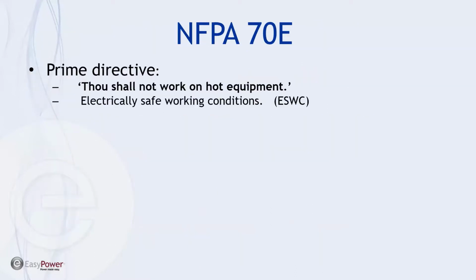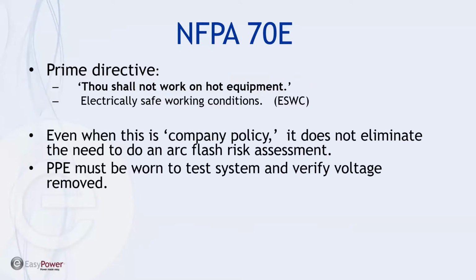So the bottom line, or the prime directive, in NFPA 70E is thou shalt not work on hot equipment. Obviously my own paraphrasing. But that means that we need to establish an electrically safe work condition. Even when this is a company policy, and that is we don't allow people to work on hot equipment, that doesn't mean that you eliminate the need for an arc flash risk assessment. And the reason for that is PPE must be worn to test the equipment before we can approach it and understand that it's been electrically secured.